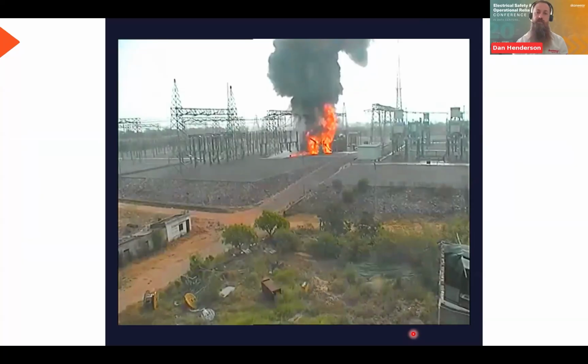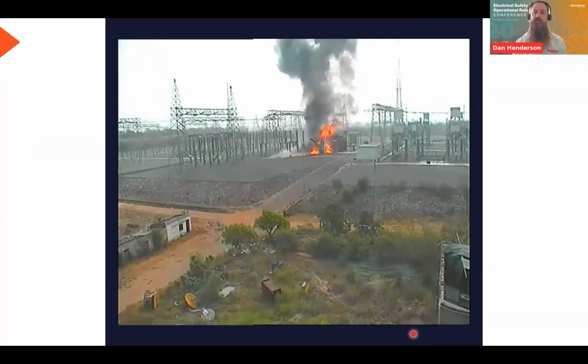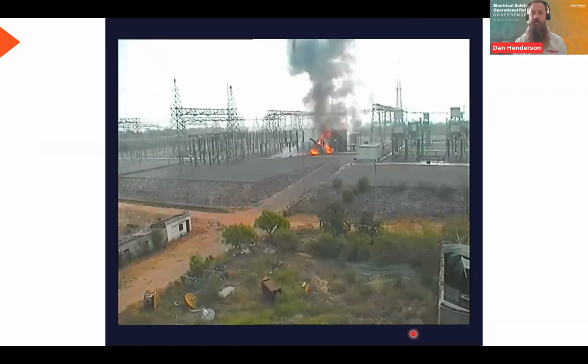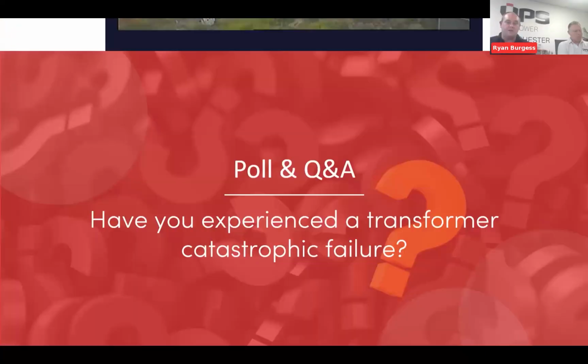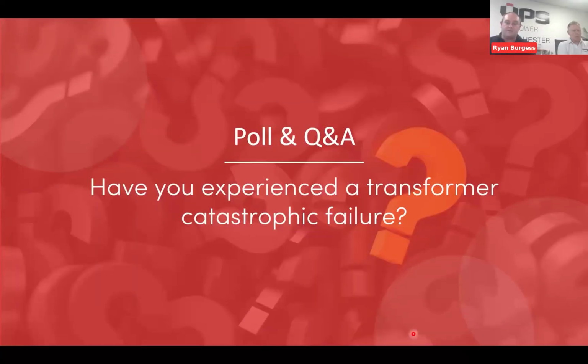So just to give us some context around the amount of energy that's there, and obviously where we've covered the flammable properties of oil, which probably will be quite heavily documented in your loss prevention and risk management guidelines or your insurance requirements. Obviously, if it's sustained and if there's still a fuel source there, then it's potential that it could go on for a prolonged period of time. And luckily that was an unmanned site, and especially with a bushings fire, bushings are made from ceramic, and as they explode, it's basically a lot of shrapnel getting thrown around and can cause a lot of damage.